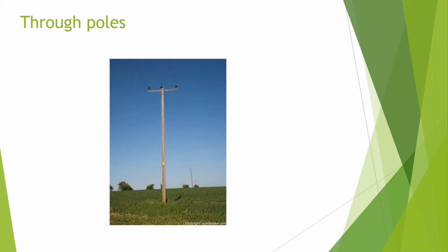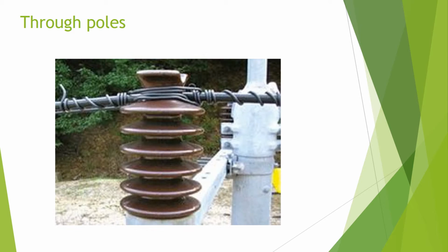Through poles are those poles that are used to support the conductors on straight sections. They feature pin insulators mounted on the top of the crossarm. These insulators maintain the safe clearance of the conductor from the metal crossarm. The conductor lays in a slot on the top of the insulator and is secured with a wire tie which is wound around the insulator and the conductor.